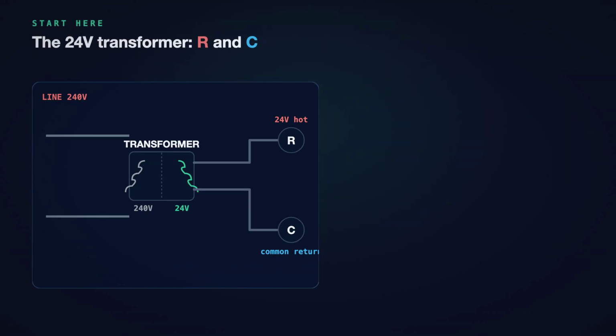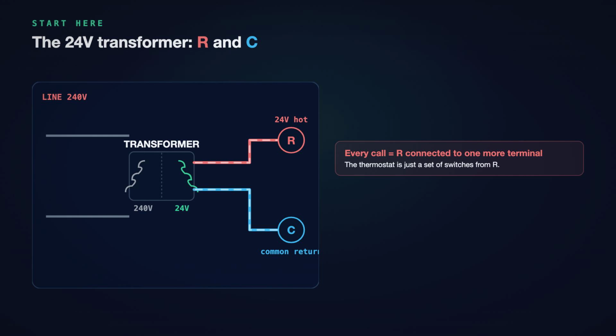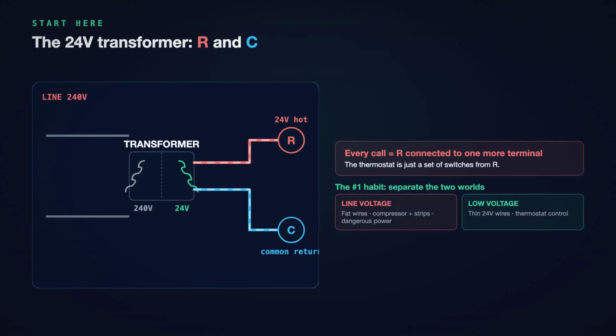Everything on the control side references two wires, so start there. A small transformer steps the line voltage, 240 or 120, down to 24 volts. That gives you R, the 24-volt hot, and C, the common return. Every call the thermostat makes is really just R being connected to one more terminal.